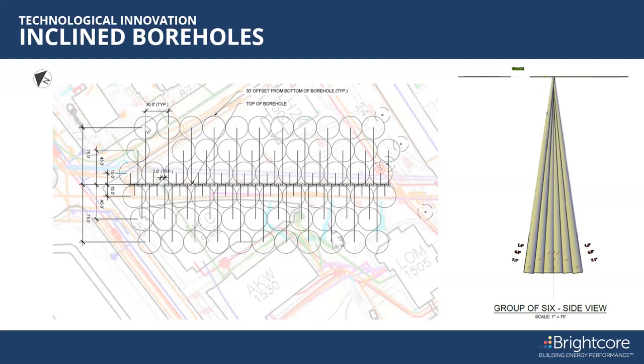Now, as an engineer, I'm not one to throw out numbers just like that. It's case by case, depends on the exchanger, depends on the delta temperature with the surface. But there's a good range that you can get. There are some boreholes that can get you 2, 3, 4 tons. There's others, based on the design, that can get 10 or 15, depending on depth, geology, ambient temperature, and other factors. But this is one way to really maximize large buildings that have larger loads that can be supported.